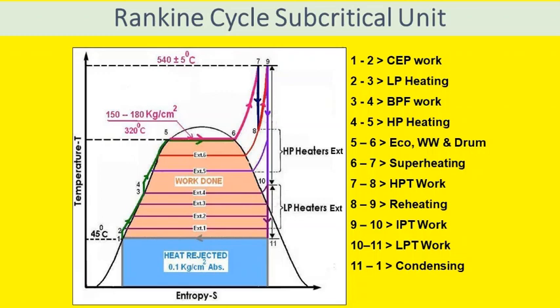Now, from 5 to 6, it represents the various stages of heating in the economizer and water wall. And as you see, our drum, the steam drum or water-steam drum, is placed outside the heat transfer zone. So water in the drum is represented by point 5 and steam in the drum by point 6, because both are in the saturation stage.